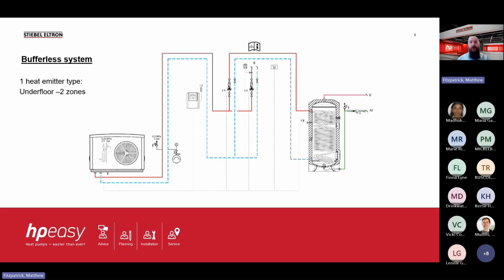So for example, if it's radiators and it's a bufferless system, the TRVs, thermostatic valves, are removed and lock shields are installed to ensure a constant flow around the system. And if it's underfloor heating, same scenario. The actuators are removed, there are no additional controls, and the heat pump and the underfloor run at a constant flow rate, always sending the flow around the underfloor, and a temperature is delivered via our heat curve.